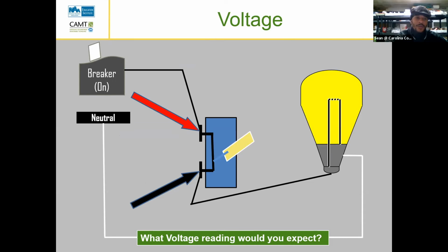240? No. It gets 0 there because you're basically testing the same thing. So whoever said 220, let me just say this. This is just a 120 volt circuit. And the way we can tell that in this schematic, for example, is that we have a neutral line. If we had a 220 volt line, it would say breaker on, and this neutral would also say line. So we'd have two lines. So it's never going to change from 120 to 240 in this scenario. So in this case, our two options are 120 volts or 0 volts.